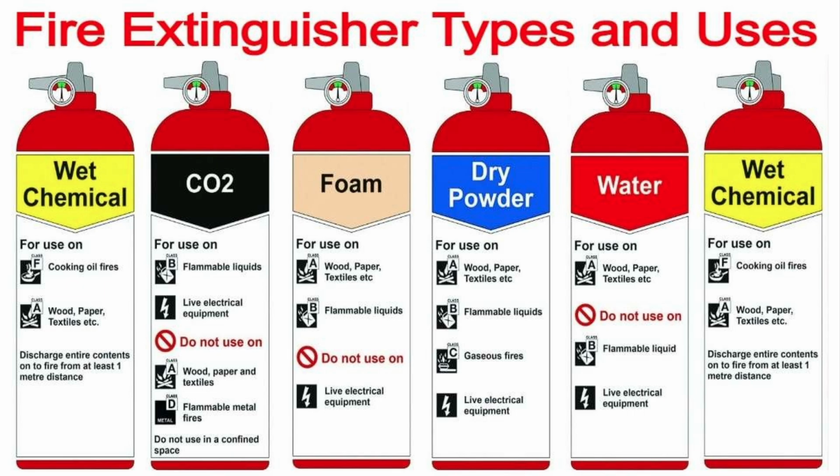Ensure that the gas penetrates casings of electrical motors or switchboards, etc. Windy conditions will detrimentally affect the medium's extinguishing capability. The discharge horn should always be held by the insulated handle only and not by the horn itself, since the low temperatures generated by discharge can cause cold burns to the skin.